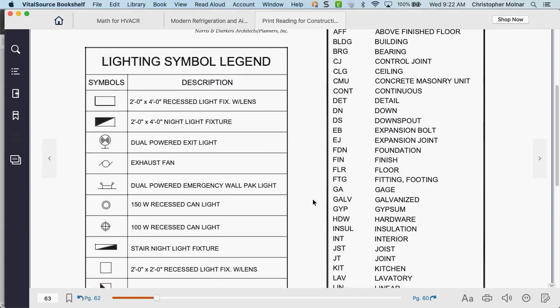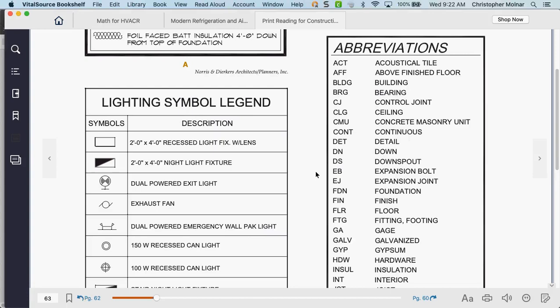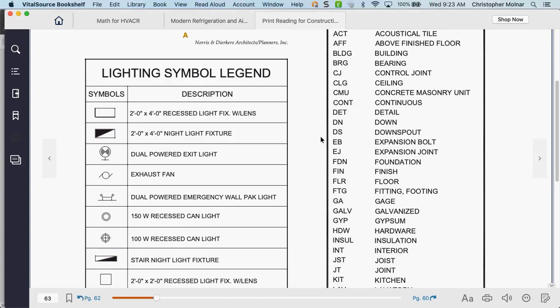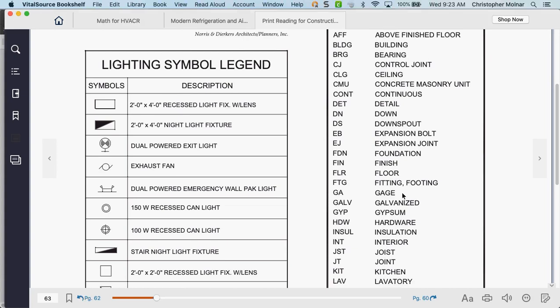Then we have abbreviations that show up on blueprints — things like acoustical tile and 'above finished floor.' Downspouts are extremely important when talking about where to place condensers. If you see a downspout labeled on the side of a building, do you want to put your condenser near it? No — because a downspout is your roof runoff. It's going to dump water onto the outdoor equipment. Not a good idea.